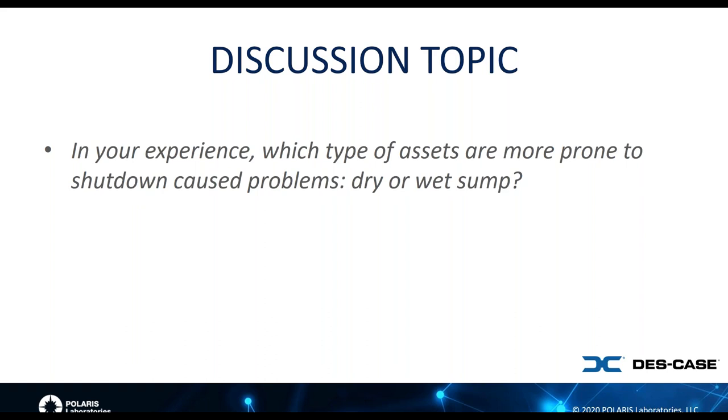Well, anything that, sorry, Bob. Anything where water can get into the system will definitely be more prone to causing shutdown problems or failures, for that matter. Anything that is exposed to water will oxidize much faster. Water can also be floating freely, which will actually cause some rust and corrosion in the system. So in my mind, wet sumps are a more prone or problematic situation here.